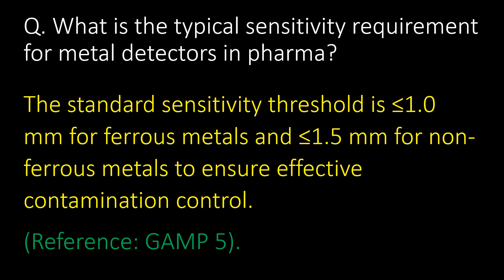What is the typical sensitivity requirement for metal detectors in pharma? The standard sensitivity threshold is less than or equal to 1.0 mm for ferrous metals and less than or equal to 1.5 mm for non-ferrous metals to ensure effective contamination control. Reference: GAMP 5.